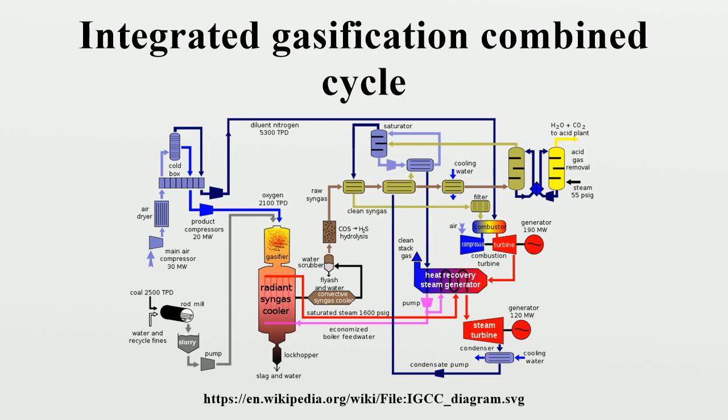With additional process equipment, a water-gas shift reaction can increase gasification efficiency and reduce carbon monoxide emissions by converting it to carbon dioxide. The resulting carbon dioxide from the shift reaction can be separated, compressed, and stored through sequestration. Excess heat from the primary combustion and syngas-fired generation is then passed to a steam cycle, similar to a combined cycle gas turbine. This process results in improved thermodynamic efficiency compared to conventional pulverized coal.